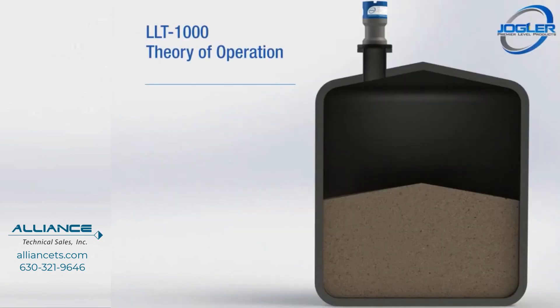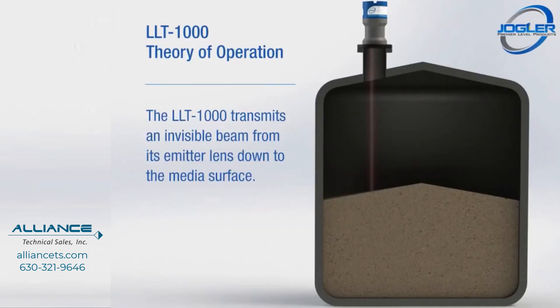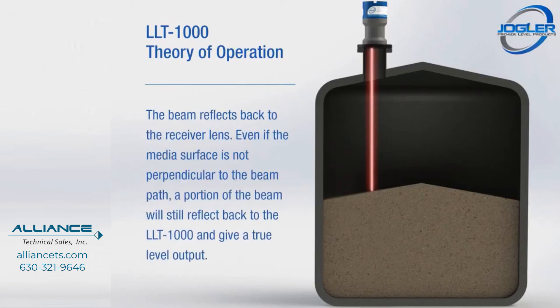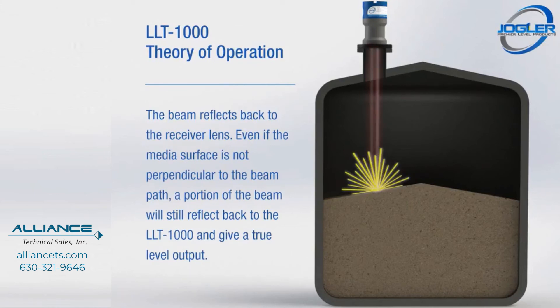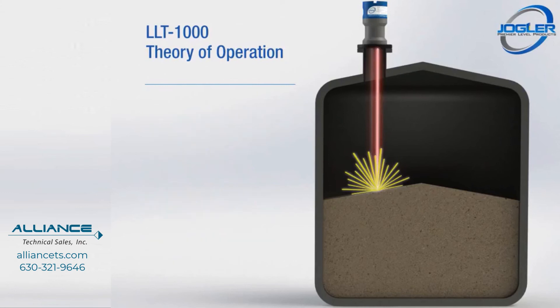The LLT-1000 transmits an invisible beam from its emitter lens down to the media surface. The beam reflects back to the receiver lens. Even if the media surface is not perpendicular to the beam path, a portion of the beam will still reflect back to the LLT-1000 and give a true level output.